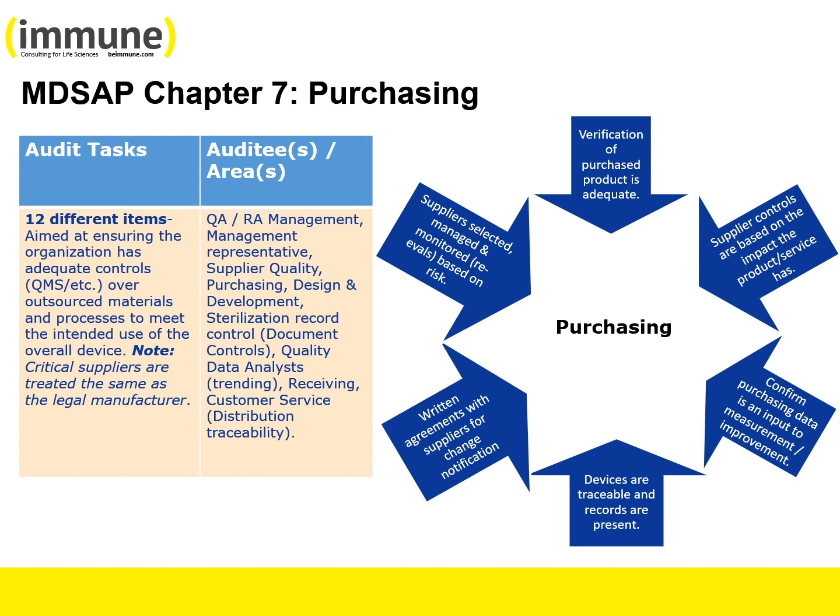Suppliers include those providers of any product received from outside of the medical device organization, including corporate or financial affiliates, where the product has an effect on subsequent product realization or the final medical device. Auditors typically tend to specifically look at those organizations who outsource activities such as design and development or production to one or more suppliers, and when the supplied product or service cannot be verified by subsequent inspection.